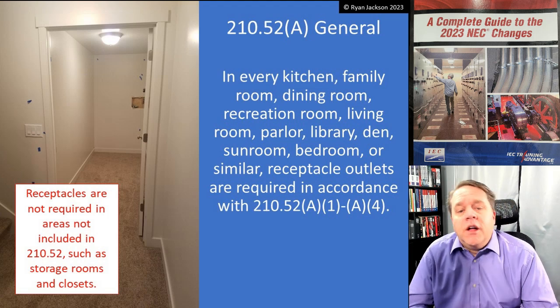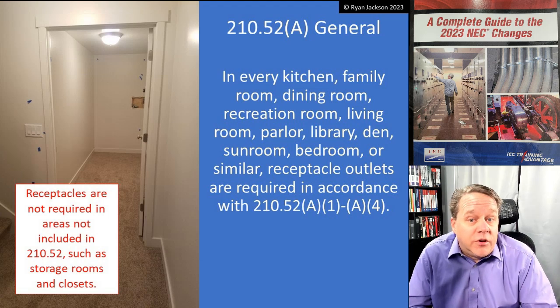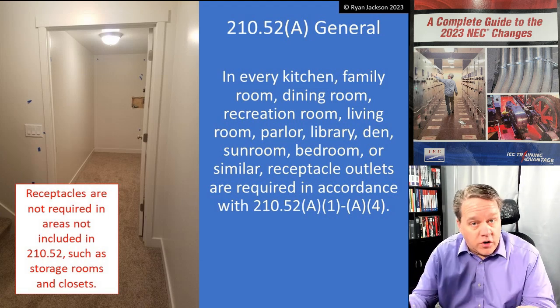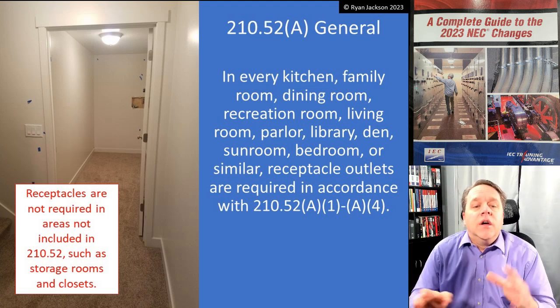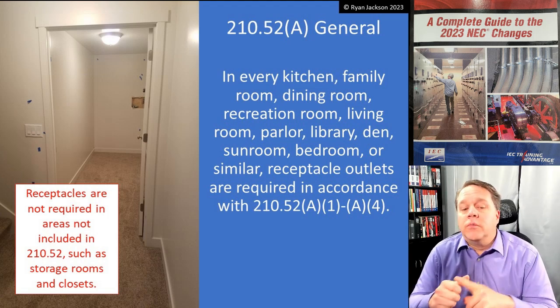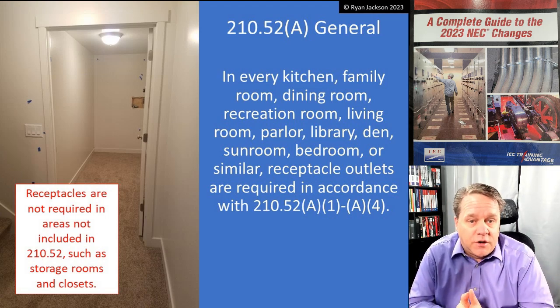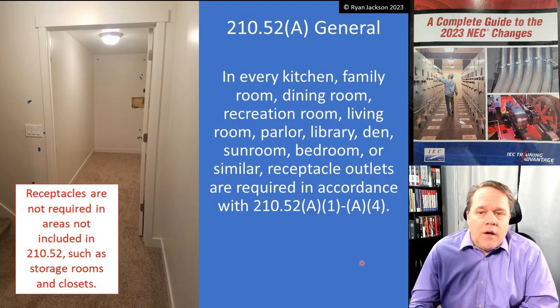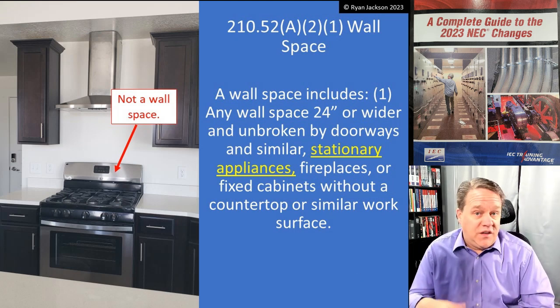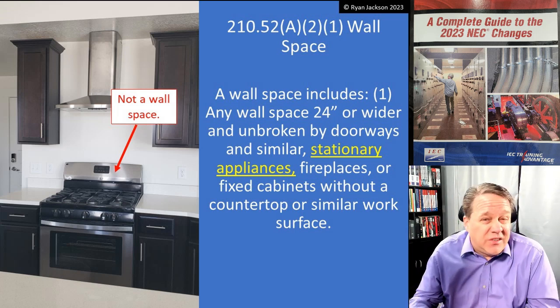210.52A — General: in every kitchen, family room, dining room, recreation room, living room, parlor, library, den, sunroom, bedroom, and similar rooms, receptacle outlets are required in accordance with A1 through A4. This is where we get our wall space requirements — the 6-foot and 12-foot layout. Only those listed rooms require receptacle outlets; rooms like closets, storage rooms, and mud rooms do not.